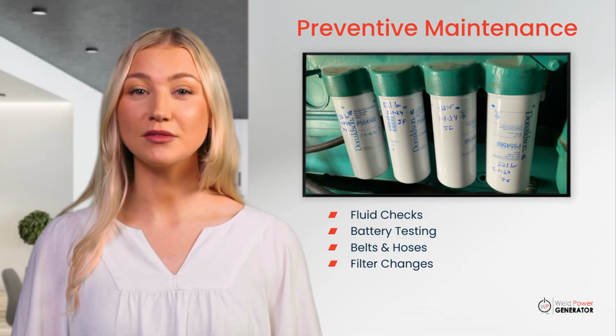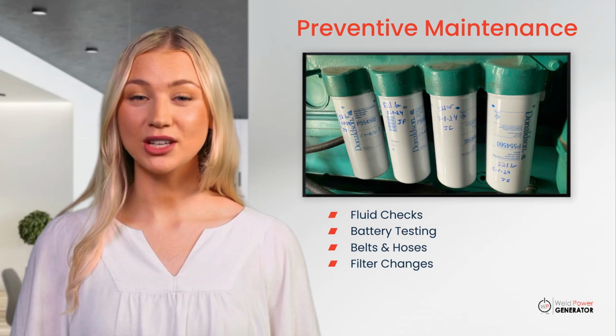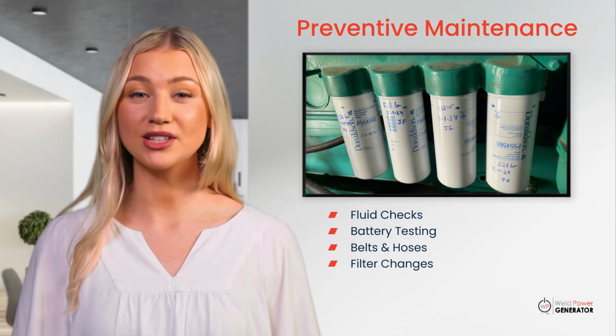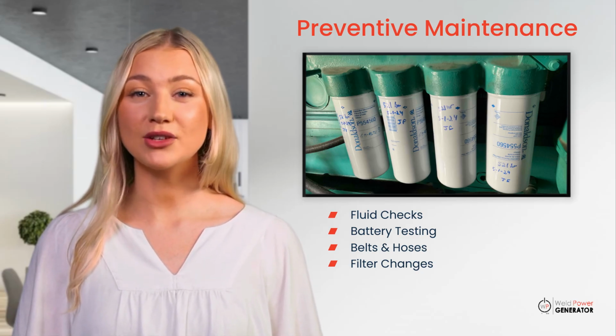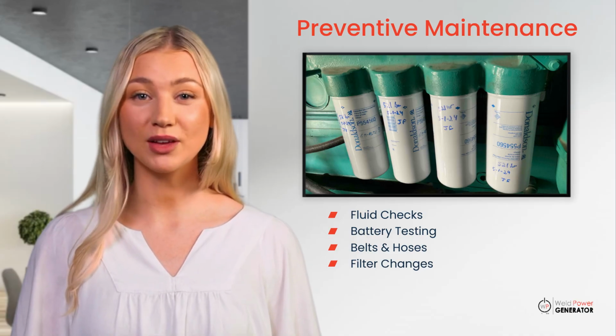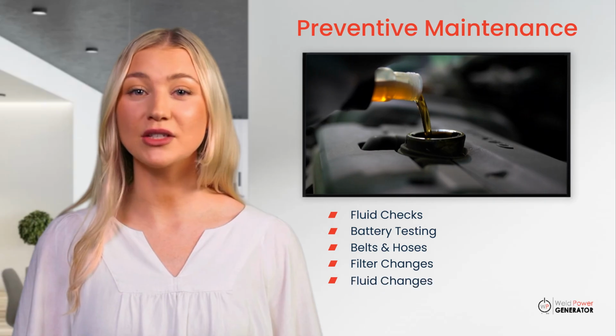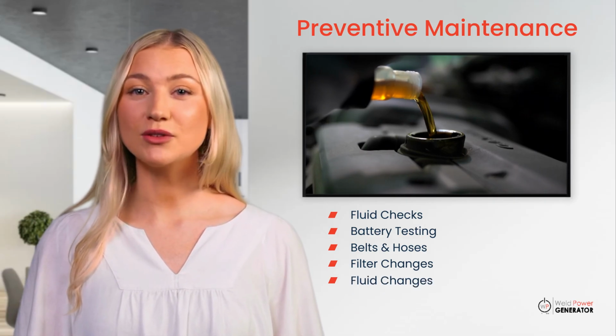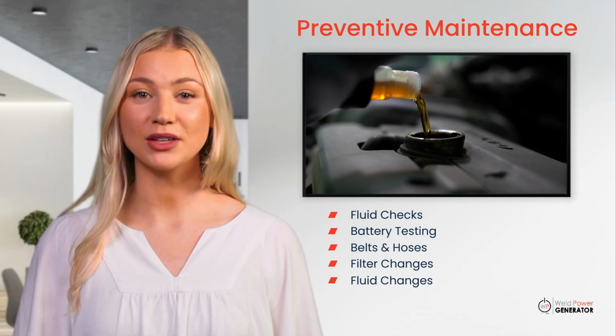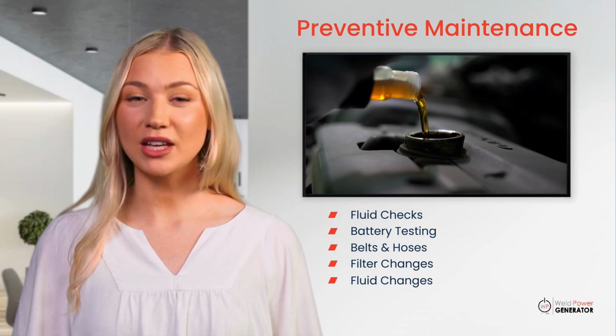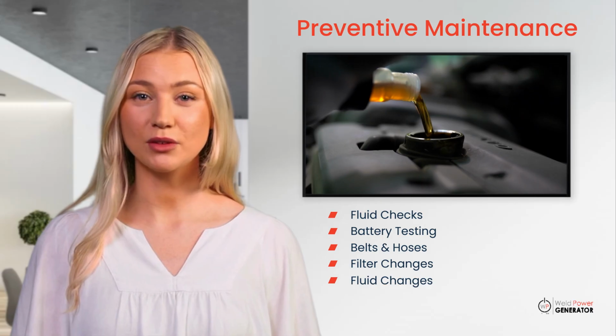Filter changes. Filters degrade over time regardless of runtime hours. Establish calendar-based change intervals, not just hour-based ones. Clogged filters force the engine to work harder and wear faster. Fluid changes. Oil, coolant, and fuel all degrade over time and need to be changed. Inhibitor depletion leads to internal corrosion that is expensive to reverse.